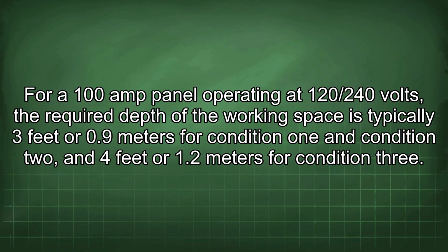For a 100 amp panel operating at 120/240 volts, the required depth of the working space is typically 3 feet or 0.9 meters for Condition 1 and Condition 2, and 4 feet or 1.2 meters for Condition 3.